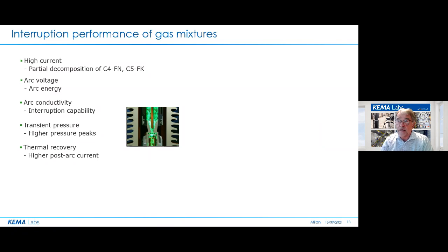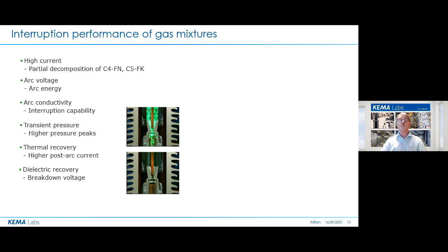Well, during the interruption process, there is a buildup of pressure inside the chamber of the breaker. We have seen reports that there are higher transient pressure peaks in the new gases. Speaking about the thermal recovery of the new type of gases, we see that the post-arc current, which is instrumental in the decay of the plasma after interruption, is higher, so designs need to be adapted to that, which also applies to the dielectric recovery of the breaker after the arc is gone. It is therefore of no surprise that for these non-SF6 gases, a new design of breaker is essential. There is no way of taking the SF6 gas out and putting the alternative gas in.